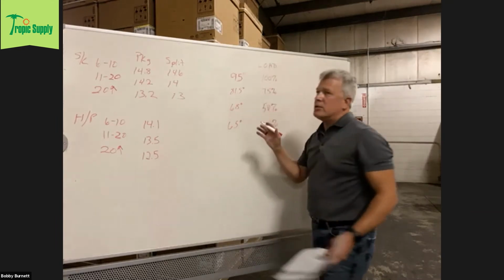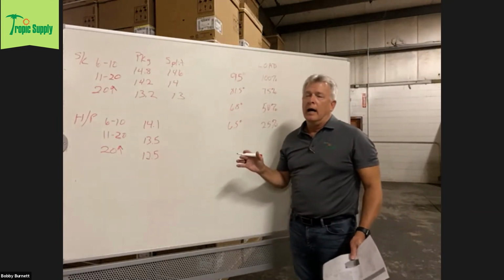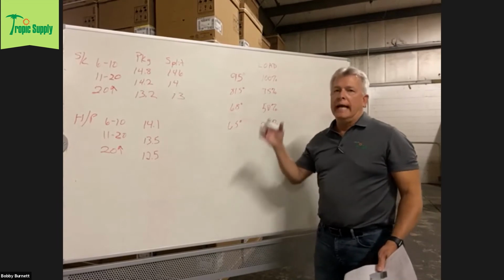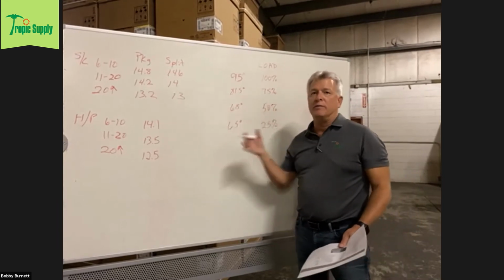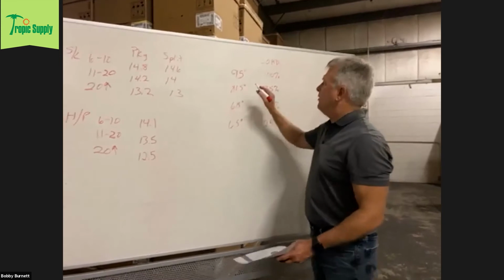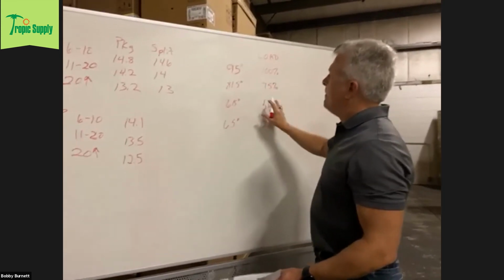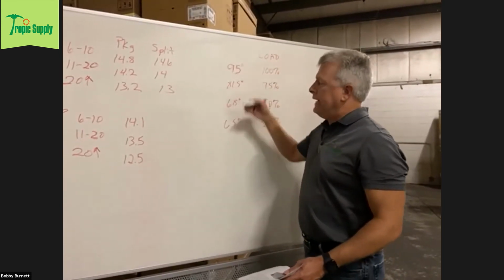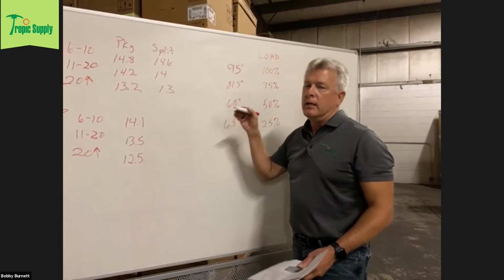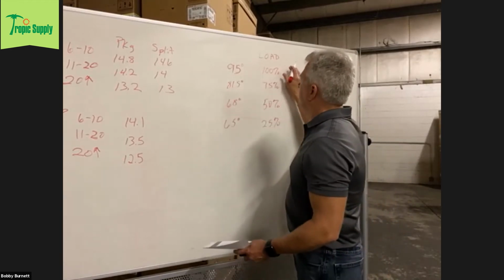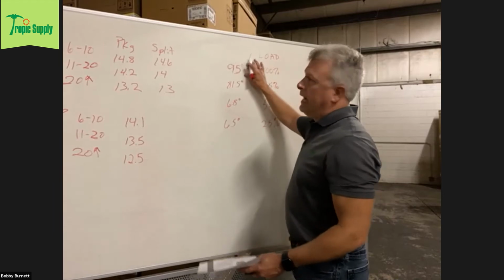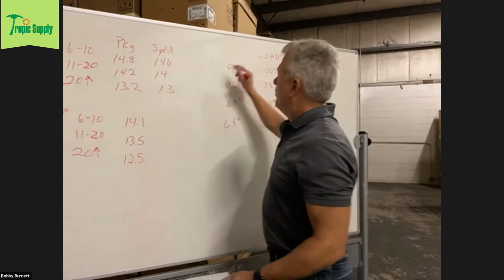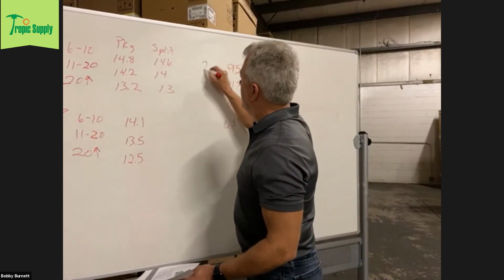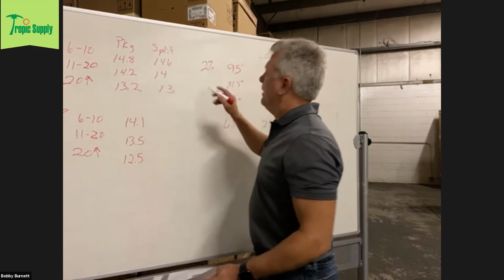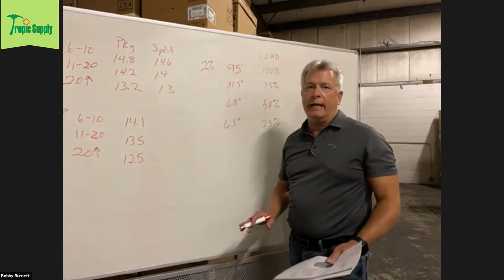So obviously your inverter equipment, your multi-stage equipment, that's going to give you a higher overall average of EER, because they're not only testing these parameters, but they're weighting what each of these parameters are differently. So for example, when they're running that unit at 100% load at a 95-degree ambient, they're only giving that a 2% weighted value of the overall IEER rate.